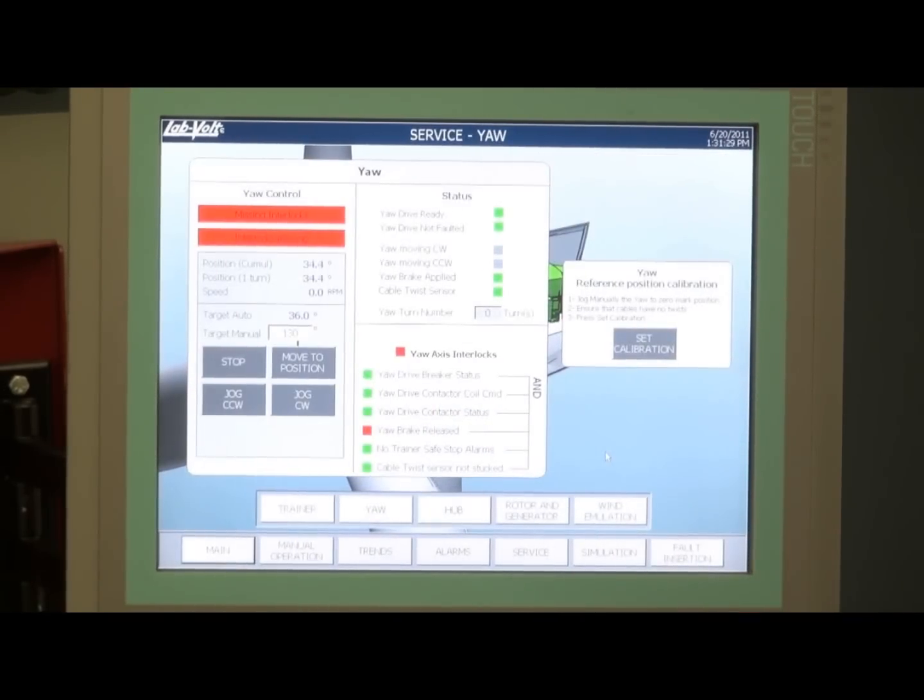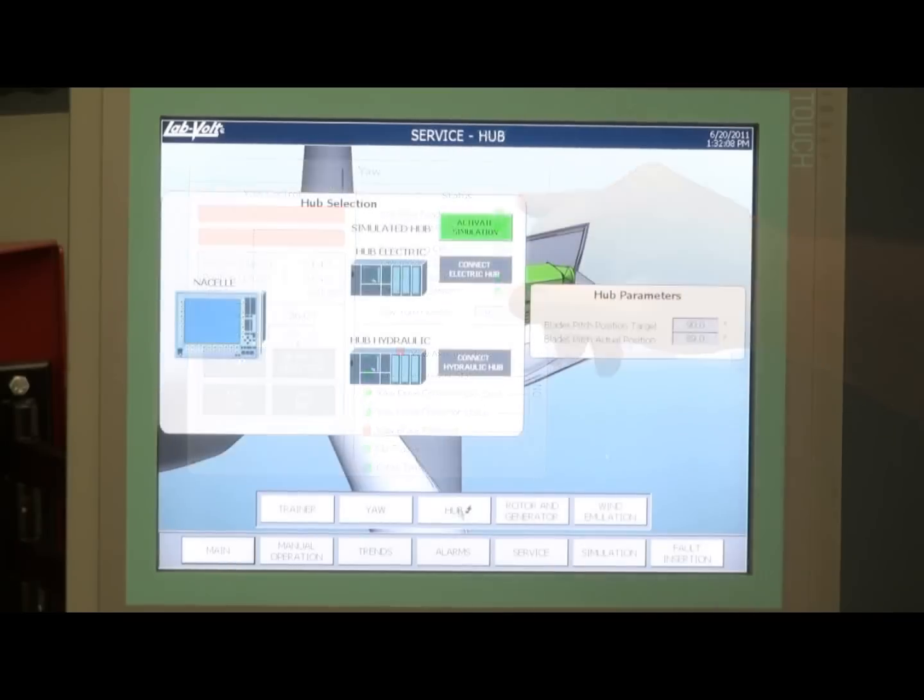Services windows are also accessible for the different parts of the nacelle, like the yaw service window, where you can see all the important parameters in the yaw operation. The yaw can even be calibrated from this section. If the user has one of the two hub trainers from Lab-Volt, the hub services window permits the user to connect one of them to the nacelle trainer, so the blade pitch command is actually performed on the hub trainer, and the feedback is sent back to the nacelle.